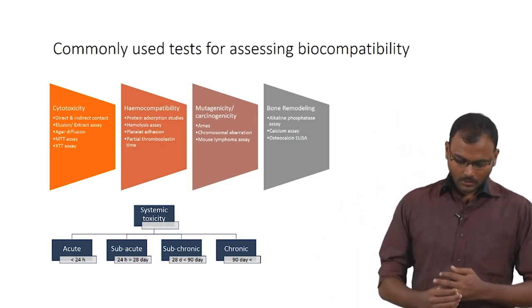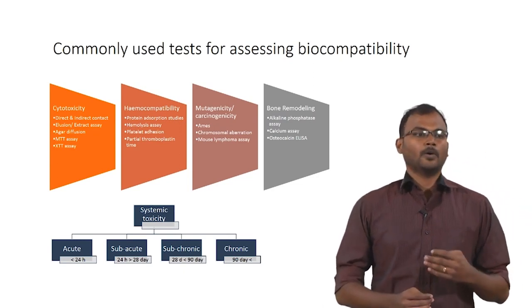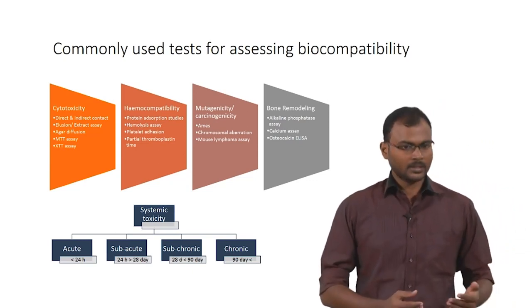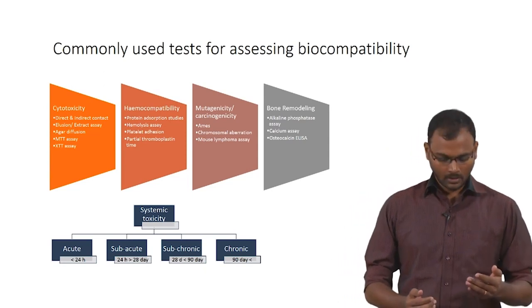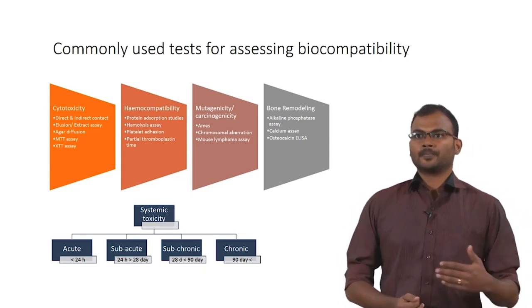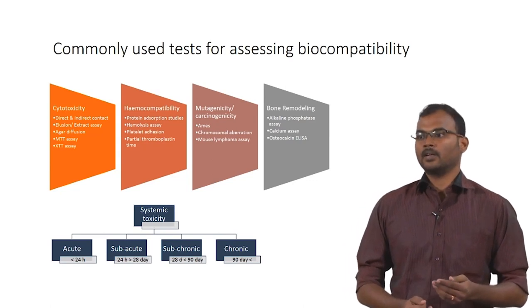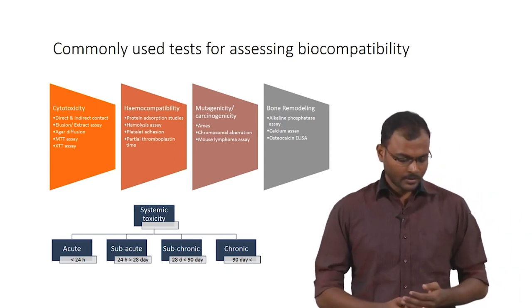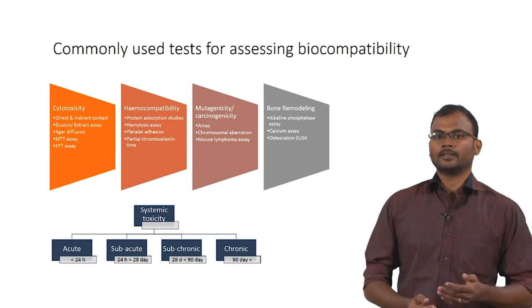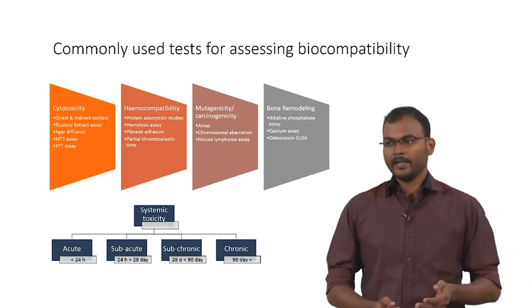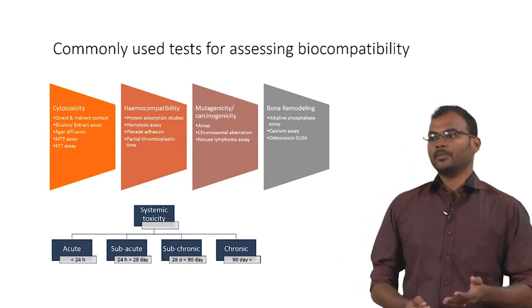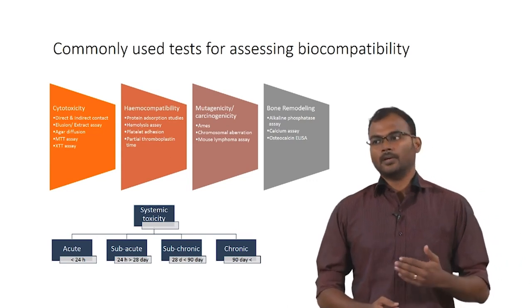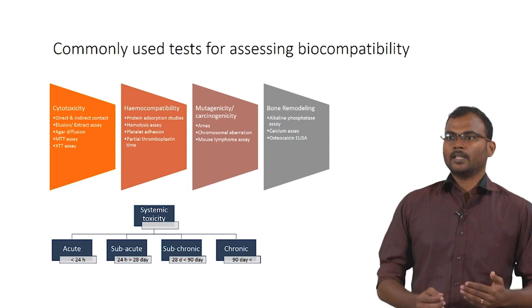Okay. So systemic toxicity depends on how long the implant is going to be used in a system. Acute is less than 24 hours, as when people use catheters to do angioplasty and other treatments, and subacute is 24 hours to 28 days. Then subchronic is 28 days to 90 days, like urinary catheters, which they will remove within 2 or 3 months.